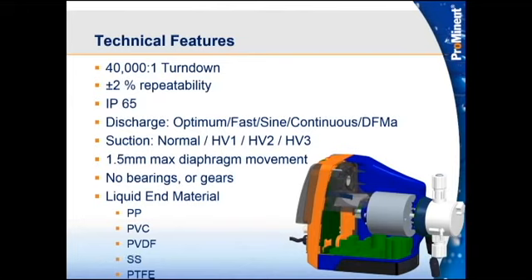Okay. The rating on the housing is IP65. The 6 stands for it's sealed so no dust can get inside. The 5 means it can take a low pressure shower of water. I would still try to protect the pump the best you can. Keep it out of the weather. None of our pumps are throwaway pumps. I wouldn't want to spend the money that our pumps or competition is charging for our pumps and say they're throwaway. Ours will last. That being said, I would recommend they're put under some sort of protective cover.